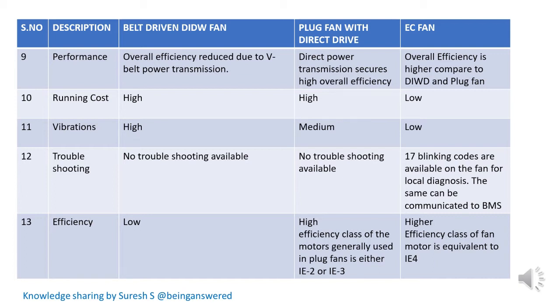EC fan will have very low running cost. Because of multiple parts and motor rotor, the belt driven system will have more vibration, whereas plug fan will have medium and EC fan will have very low vibration. For troubleshooting, there won't be any troubleshooting hints available to identify faults in belt driven or plug fan. But in EC fan, we will have multiple inputs received if there is any abnormal condition, making it easy to diagnose, and it can also be communicated through BMS.